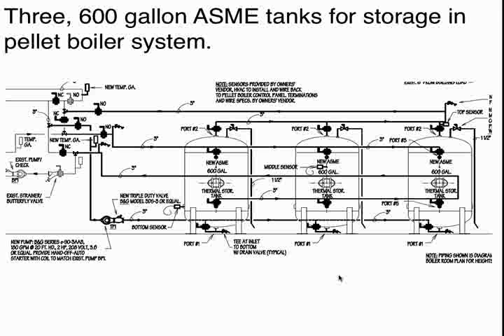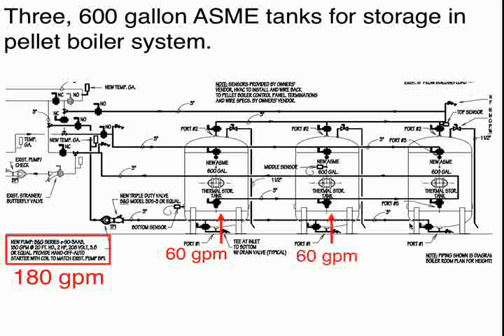This is a drawing that we had a chance to review. This is, again, a large commercial pellet boiler system, a 1.7 million BTU per hour system. And just looking around at some of the notes, I noticed this note down here. And that note says, essentially, you may or may not be able to read it, that this pump is moving 180 gallons per minute of flow down through this 3-inch pipe. And if you follow where that pipe goes, it basically goes into the bottom of this tank, as well as the bottom of that tank and the bottom of this tank. In other words, the flow divides up like this, 60 gallons per minute going vertically upward into the bottom of each of these 3 tanks.